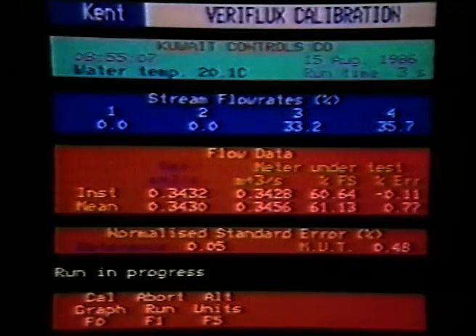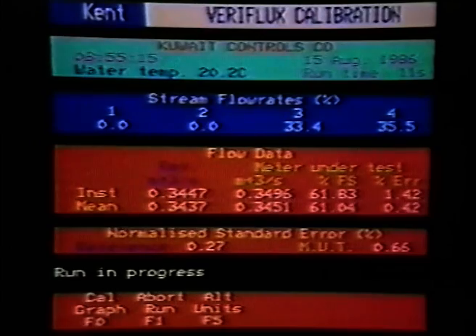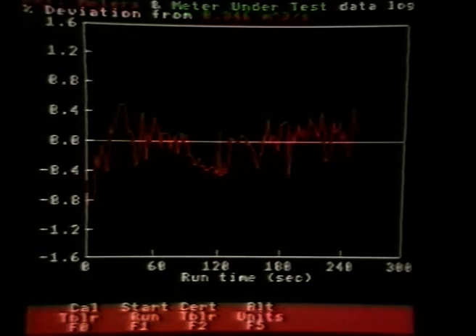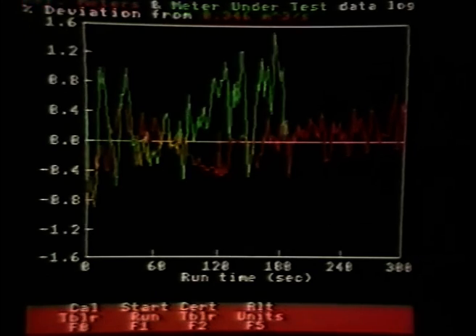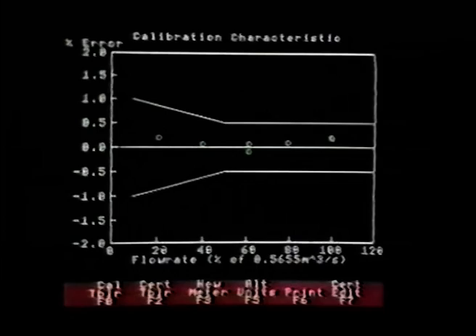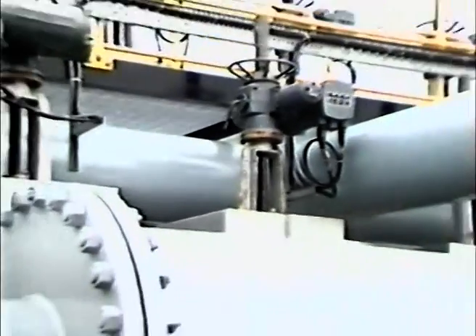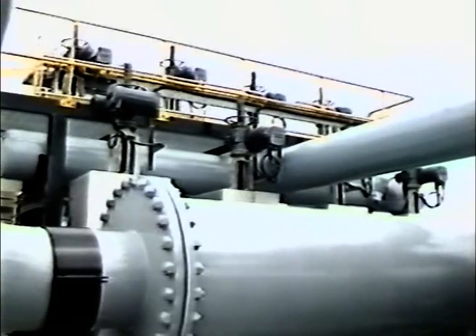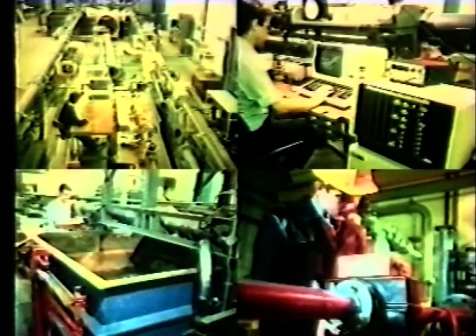This first display shows a typical Veriflux calibration run with customer information, the date and so on. It also gives information on, for example, flow rates through the transfer standard meters and the meter under test, and real-time data of flow characteristics. This display is a calibration graph of instantaneous readings. These are tabulated values. And here is the calibration characteristic, which is printed out here on the customer's calibration certificate. The test system is entirely automatic, and it's impossible to enter test data via the keyboard, so the integrity of the test is guaranteed. An important feature of the plant is that the computer automatically applies temperature compensation during the test. The large calibration rig is only one part of the overall Kent flow calibration capability.